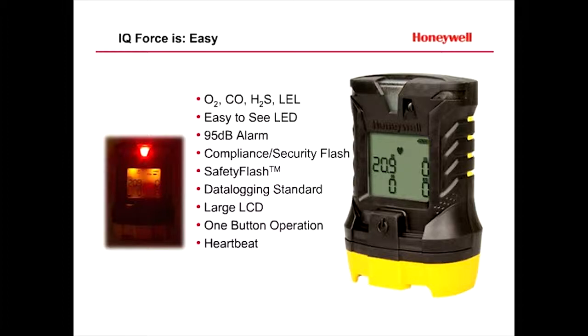Let me explain Compliance Flash. If you're working in a situation and you want to be able to see from a distance that the detector's on and working, enable the Compliance Flash. What this does is it flashes the red LED every few seconds so that from a distance you know that the instruments are turned on and working. You can just look at your crew and you'll see red flashing lights.